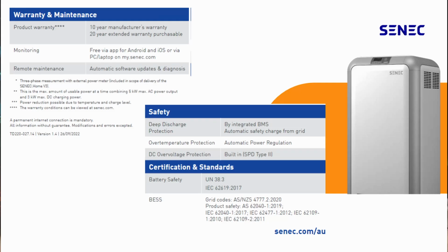Cool. The battery modules, are they high voltage batteries? They're low voltage batteries. They're lithium-ion NMC modules. Okay, so nickel, manganese, cobalt, and nominal voltage is around 58.1, or that's their peak. Correct. Cool. So in terms of cycle life, or energy throughput, do you give any warranties around that? Out of the box, we give a 10 year warranty, 12,000 cycles, and 75% capacity remaining after that. How many cycles? 12,000 cycles. That's unheard of. So obviously very, very good quality batteries. We're very confident. You probably won't live long enough to use them.